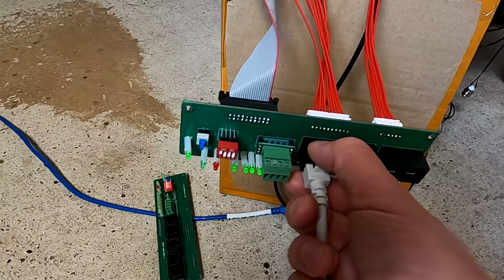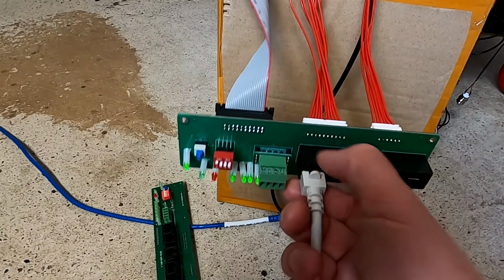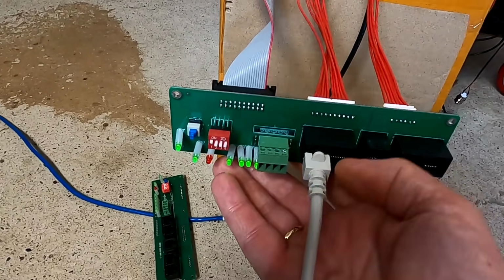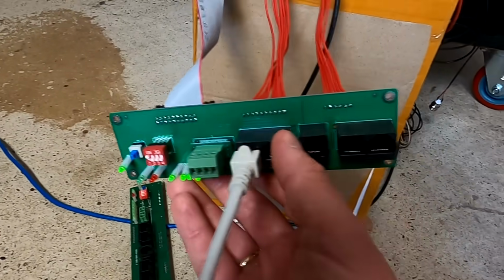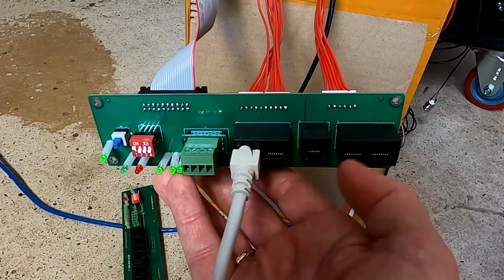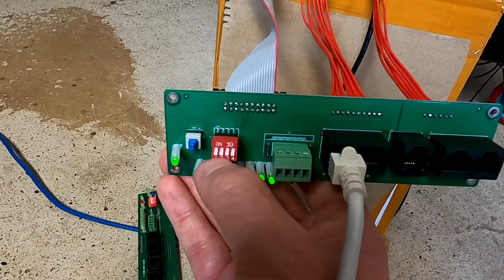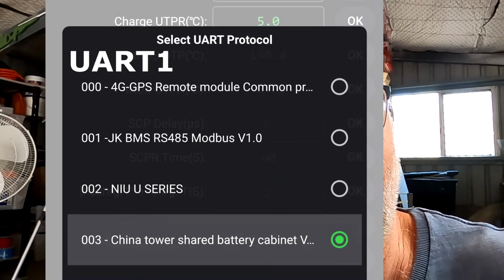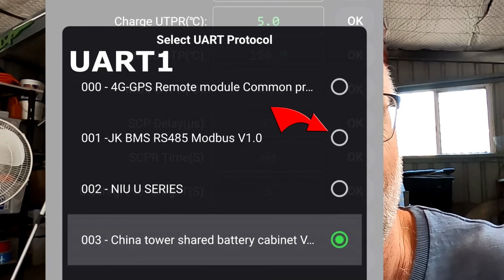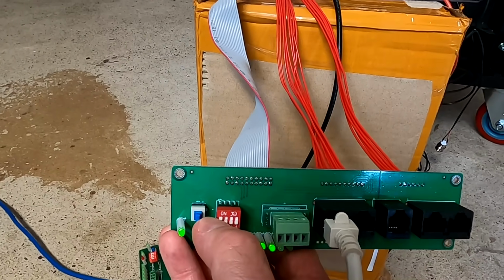So, very long story short, JK is now sending out a new BMS - they think it might be faulty for whatever reason. At the moment, the communication is only working through the RS485 port of the inverter. So if you get your BMS and it's not communicating through these 2 ports here on the right, set all the dip switches to 0, go into the app and set the UART1 to the JK protocol, then turn on dip switch 1. This is the sequence you need to do to connect to the computer software.